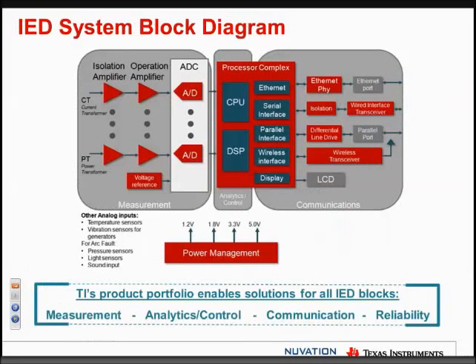Looking at the system in more detail through the block diagram: with the sensors, there's a lot of analog data coming in. As the first piece, measurement, we have a lot of ADCs converting this analog data to digital and feeding it into the processor, or the brain, of the IED. The processor itself has the CPU, memory, and controller unit doing much of the control functions. The analytics, depending on the level of sensor integration, could be handled by a DSP performing the analytics. The communication piece is essentially plugged in through the peripherals of the system, via Ethernet, serial, parallel, or similar interfaces. The overall system reliability spans measurement, analytics, and control, all the way through communication.